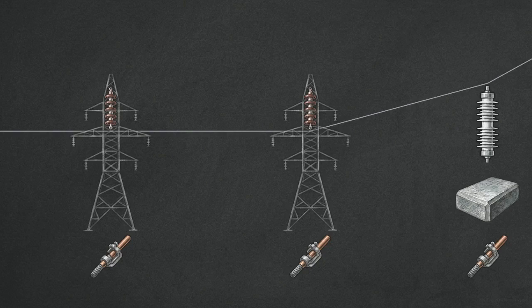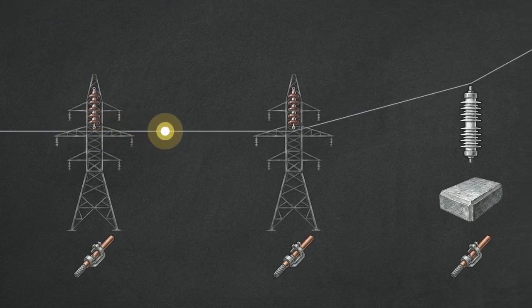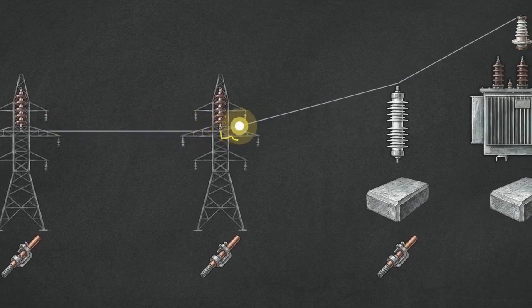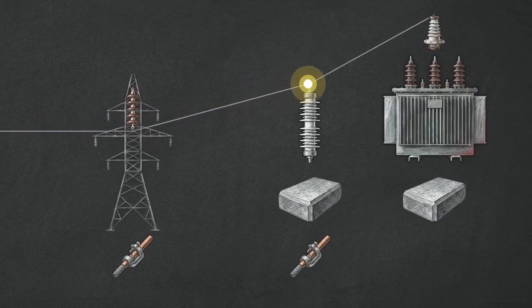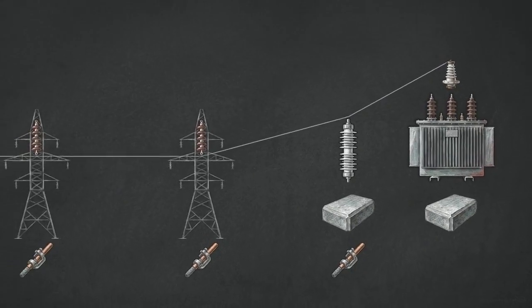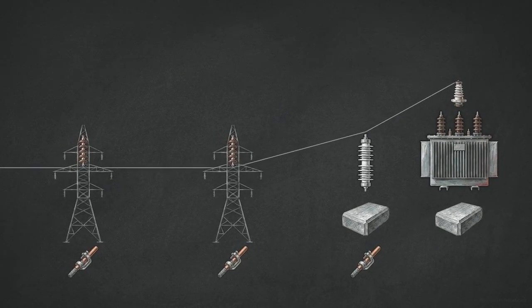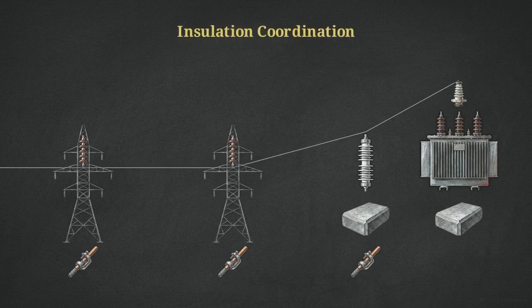When lightning strikes a transmission line, it sends a massive electrical wave hurtling toward your most expensive equipment, the transformer. But before it can cause a catastrophic failure, it's intercepted and driven into the ground by a surge arrestor. Protecting the system requires a coordinated two-part defense strategy.